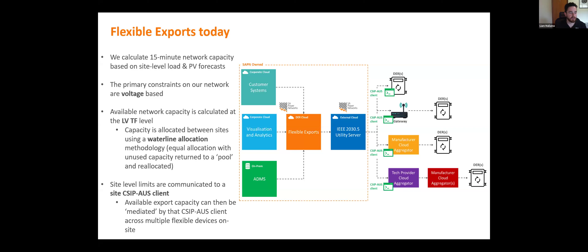We communicate limits to a site, not to an individual inverter — it applies to any devices operating at that house. We communicate via a CSIP Oz client. If there are multiple devices behind the meter — multiple PV inverters or a PV inverter and a battery — the CSIP Oz client can sub-allocate the capacity it's given to devices behind the meter where the technology exists to do so. So we allocate network capacity to a home, and the CSIP Oz client can then allocate that capacity to individual devices.